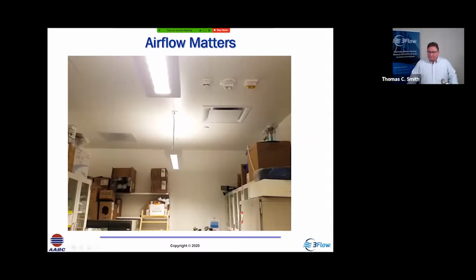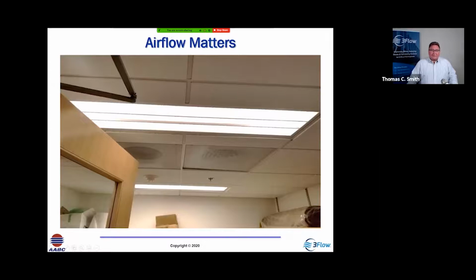Now we have the location of the supply diffusers. In this case, the supply diffuser is short-circuiting. It's also not properly located, so it's not going to get the performance out of this type of diffuser. Other circumstances where the diffuser is close to the hood or close to the exhaust, how effective is this going to be? We may be getting the right flow, but we're not using it to the advantage of conditioning or mixing in the space.